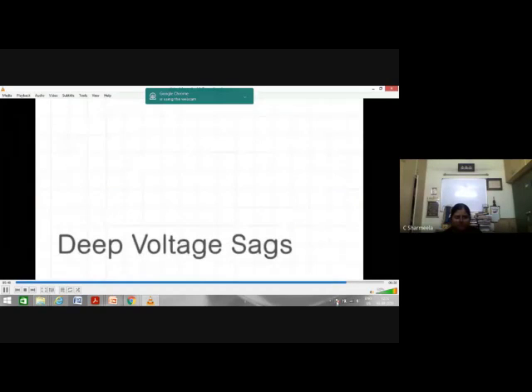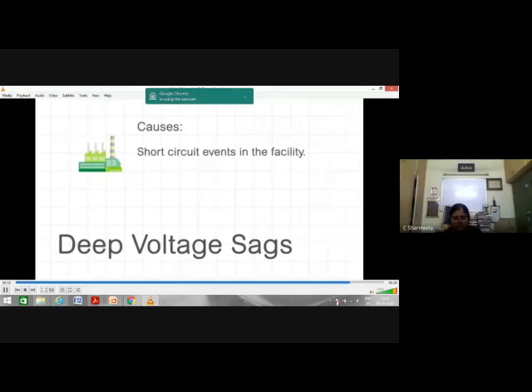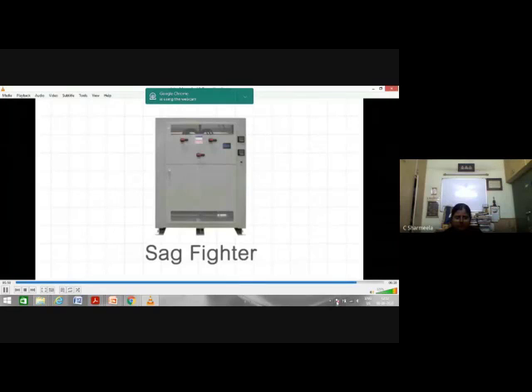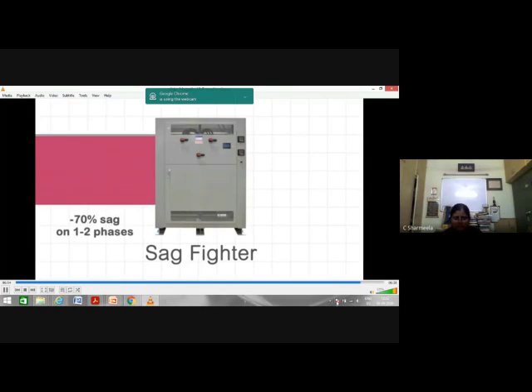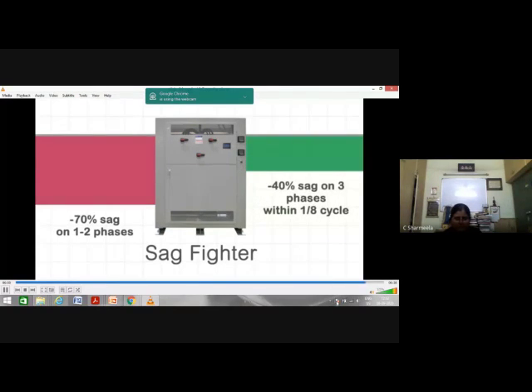Deeper voltage sags are normally caused by short circuit events and or by operation of a utility recloser. For these deep sag events, the Sag Fighter is the solution. It can correct for 70% sag on 1 or 2 phases, or for 40% sags on 3 phases within 1/8 cycle, and boost the voltage back to 95% of nominal value.